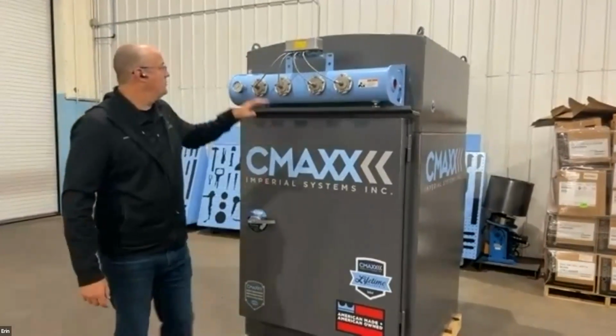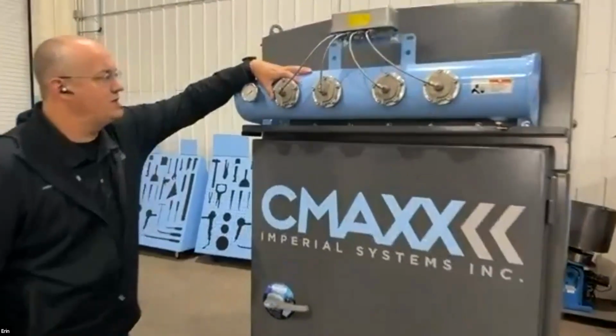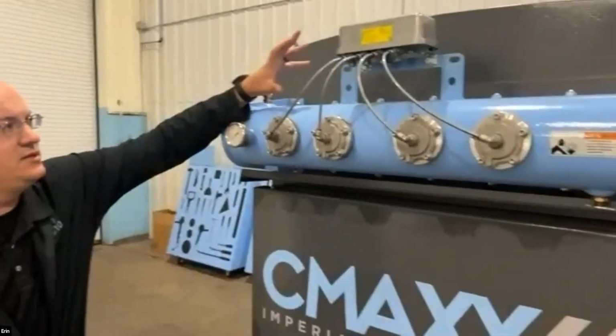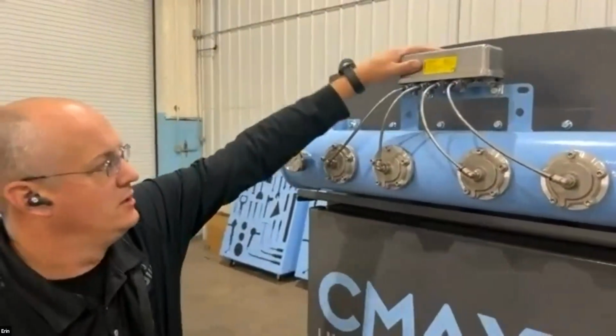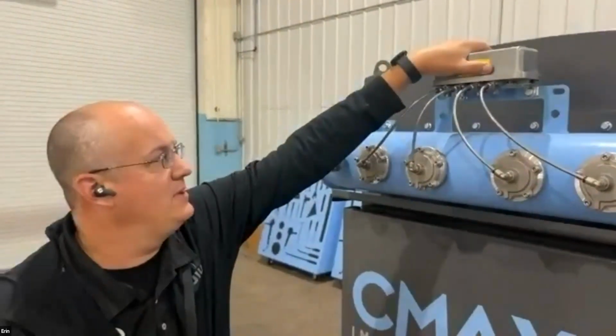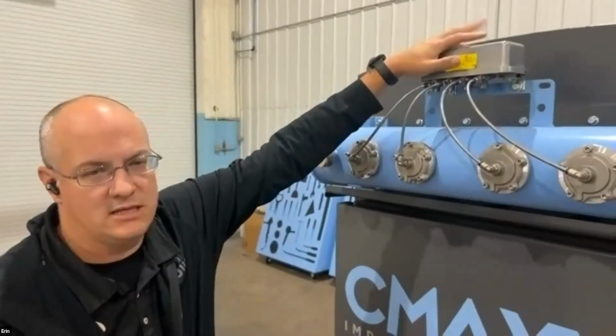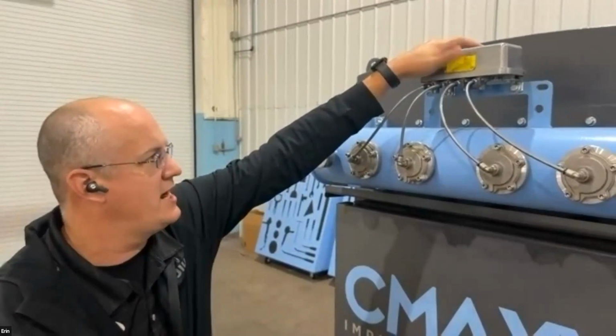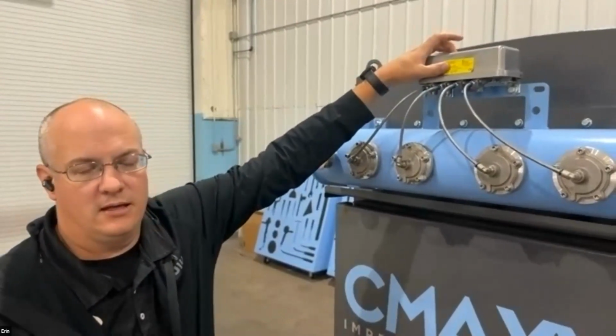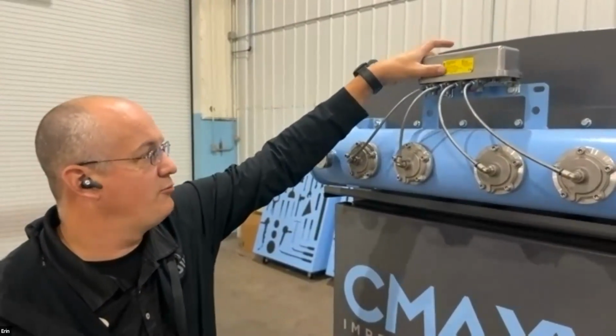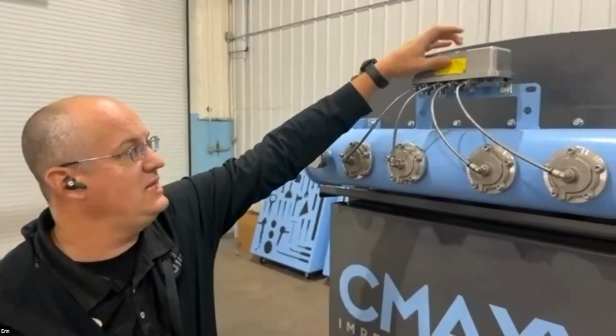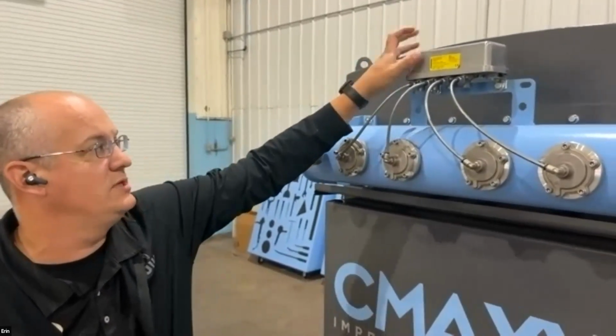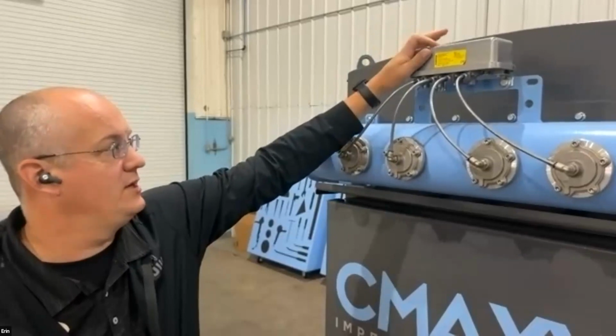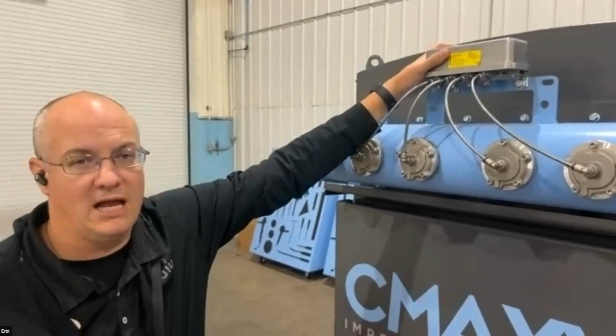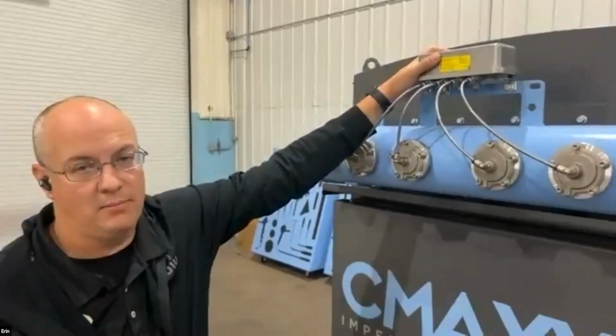Yeah, so up here we have the solenoid enclosure. In colder climates, if you have a little bit of moisture in your air, you may get these frozen up in the wintertime. So there's a heating element that can be put into these solenoids. It's simply wired in to keep this running properly in colder climates.